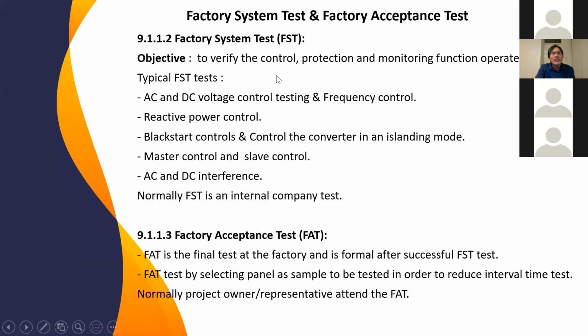What is FST? The objective is to verify control, protection, and monitoring functions operate correctly. Normally, we test all the cubicles in FST. FST is an internal company test, so we only do it internally. When we have completed successfully, we will invite the client for FAT, factory acceptance test. FAT only selects panels as a sample to be tested in order to reduce the test interval time. Otherwise, it will be longer for the customer to stay. The project owner or representative normally attends the FAT for control and protection.